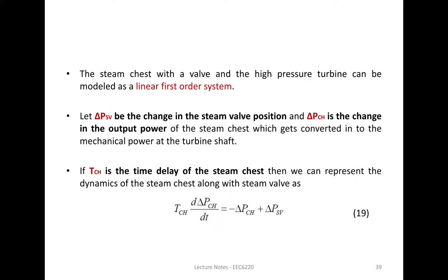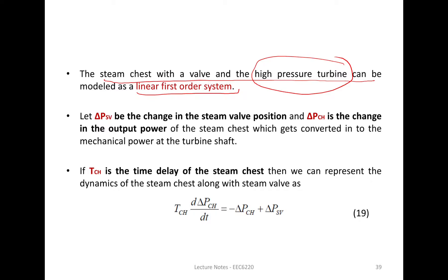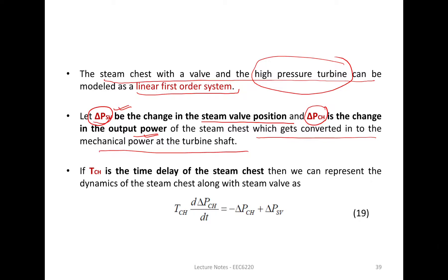The steam chest with a valve and the high pressure turbine can be modeled as a linear first-order system, since we are giving steam in and getting power output with no hindrance between them. Here, delta PSV is the change in steam valve position, and delta PCH is the change in output power — that is, the change in steam chest power which gets converted into mechanical power of the turbine.